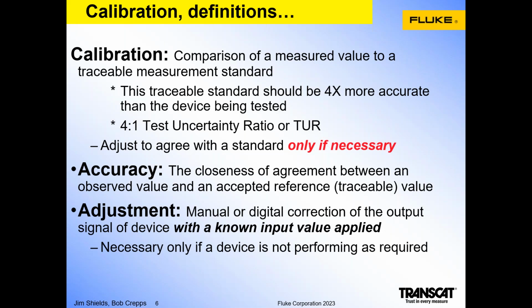that's not always practical. An example is pressure: to achieve a 10-to-1 ratio, instead of being able to use a portable gauge or a calibrator, you might have to take a bench calibrator out to do the calibration to get that 10-to-1 ratio. So the 10-to-1 is a great ideal, but it's not practical in most instances.